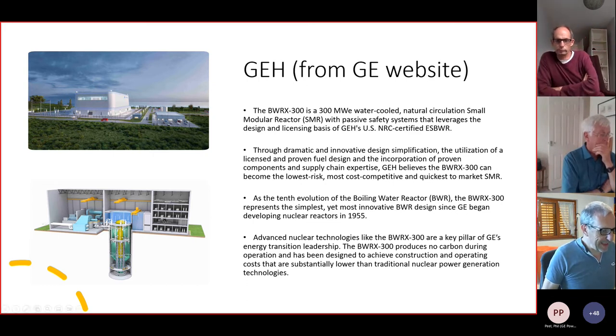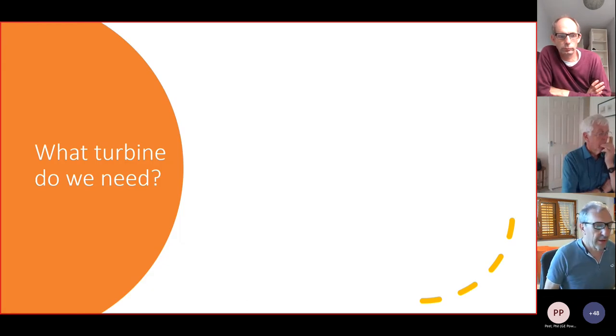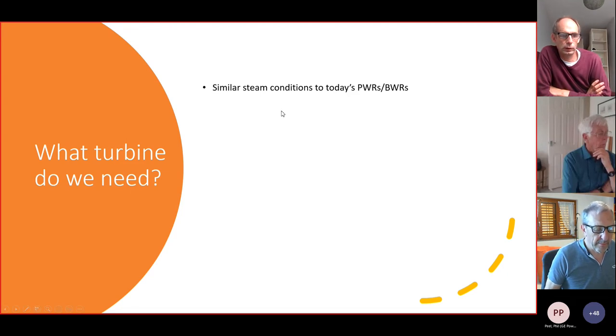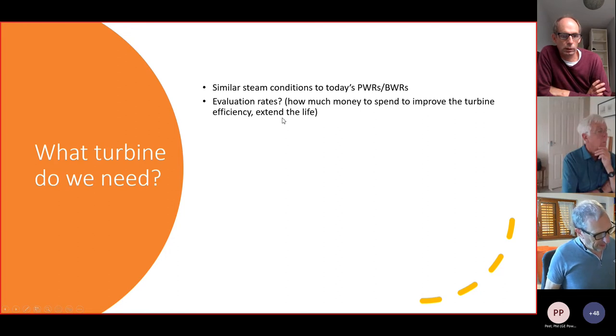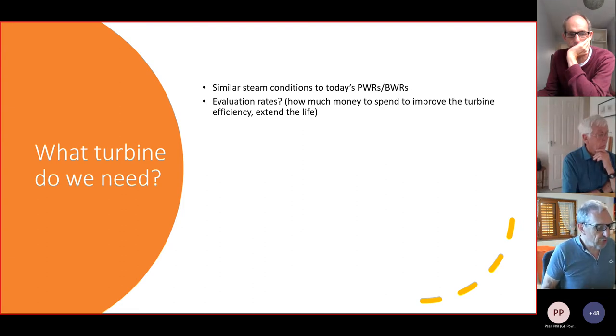These are all essentially BWRs or PWRs with very similar steam conditions — the ones relatively close to market. So what does that tell us about the turbine design? It's a PWR expansion, like Flamanville, which tells us about the steam. It's obviously less steam because it's smaller, but very similar steam conditions. When designing a turbine, the evaluation rate is a very critical question — how much cost do I put into this machine to make it more efficient? In most stages, you put up the cost and you improve efficiency.